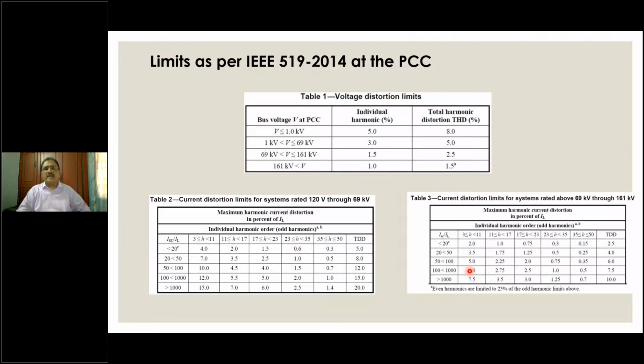These are the limits for IEEE 519 2014 for various parameters. This part is not applicable in our country anyway. From here it starts as per the regulation. From 11 kV to 69 kV is one bandwidth. 69 kV to 161 kV is another bandwidth. Above 161 kV is the third bandwidth. So these are the three bandwidths we are worried about: 11, 22, 33. And then you will find 110. Some people will also have 66, but you will find 110 and 230 kV. These are the various grid levels available in our country for industries.